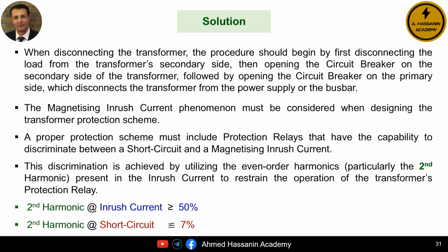The second and most important point is related to the protection device of the transformer. As we mentioned earlier, magnetizing inrush current is a distorted waveform that contains harmonics. The key point here is that when we analyzed this distorted waveform, we were surprised to find a large percentage of second harmonic components, which can be as high as 50% or more. However, the percentage of second harmonic components in a short circuit current is no more than 7%.